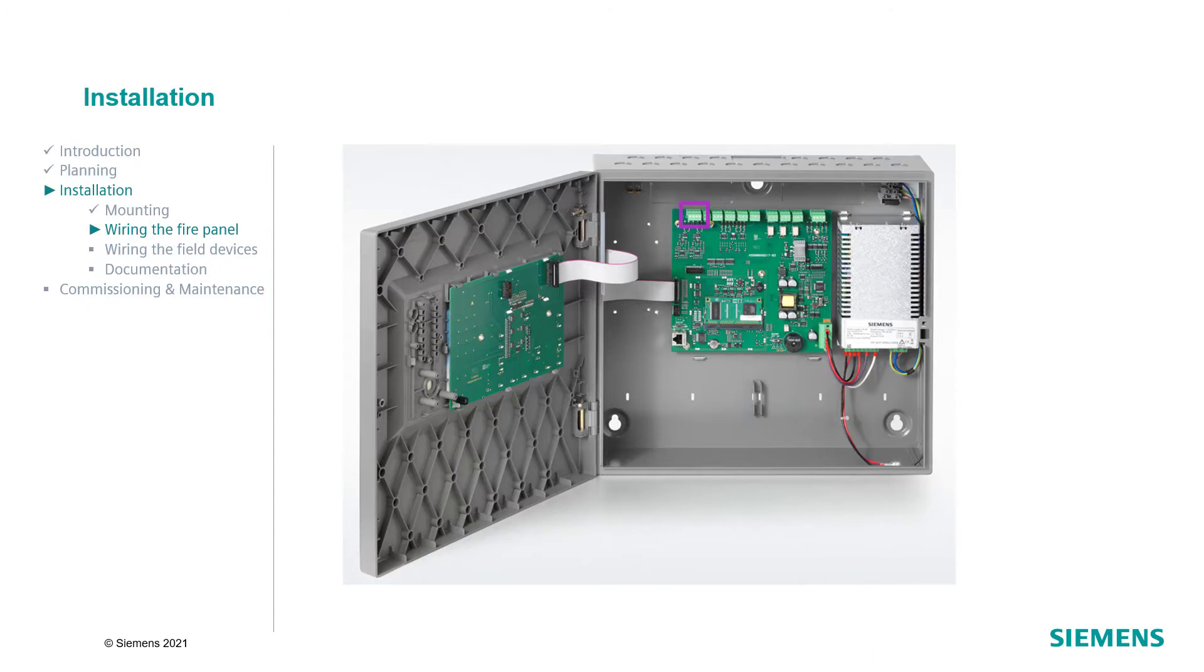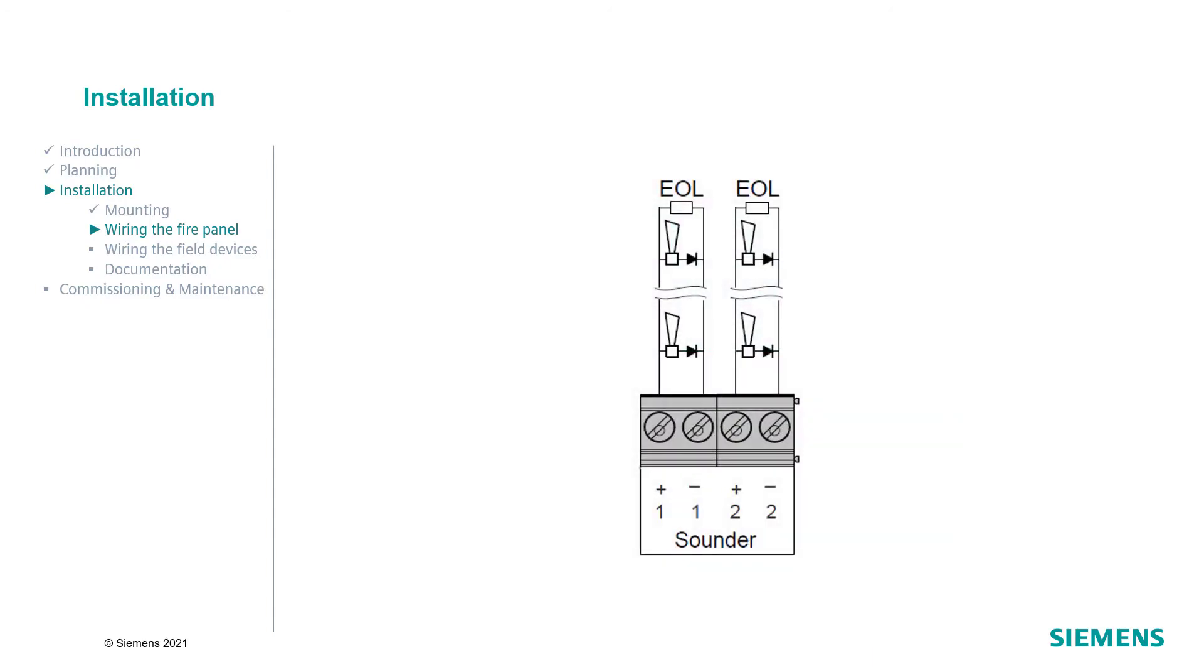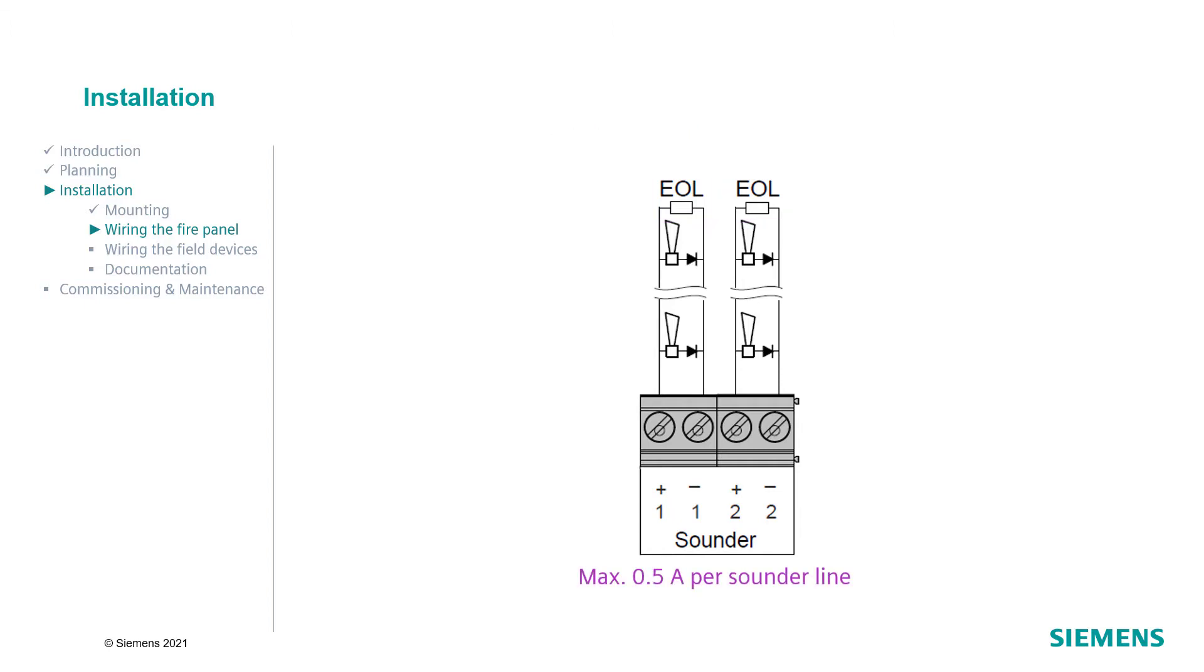The next step is the connection of the sounder lines to the sounder line outputs. Each line must be terminated with an end-of-line resistor with 2.2 kOhms. The current of each sounder line is maximum 0.5A. For both sounder lines, the maximum current is 0.5A in total.